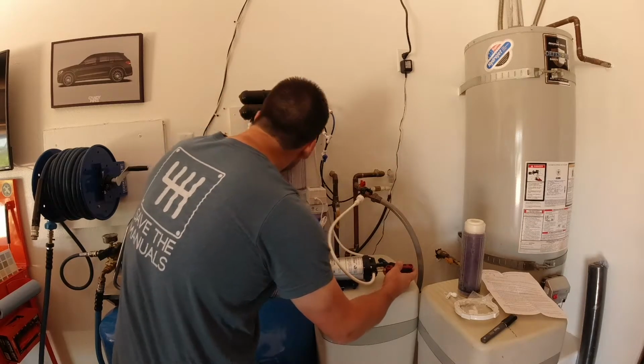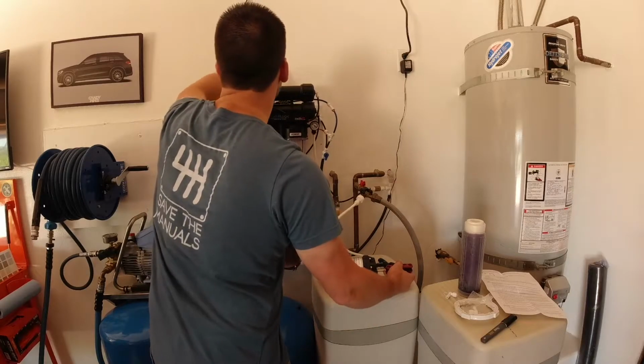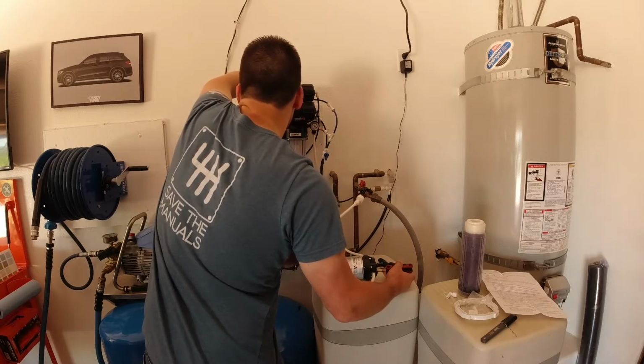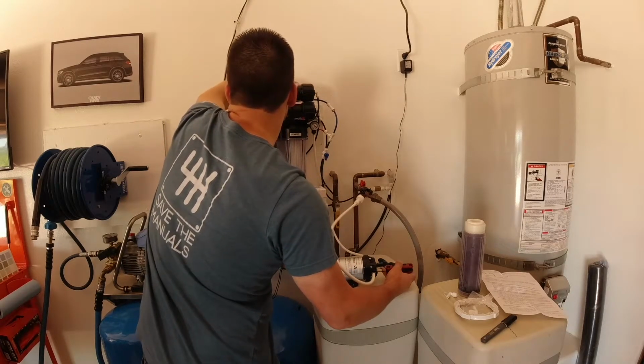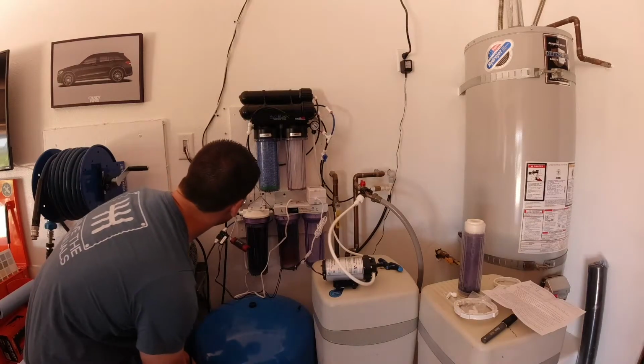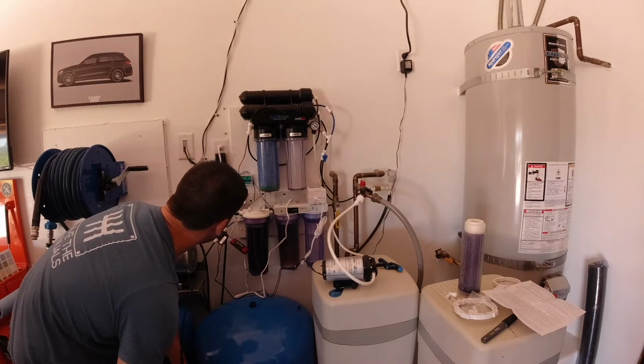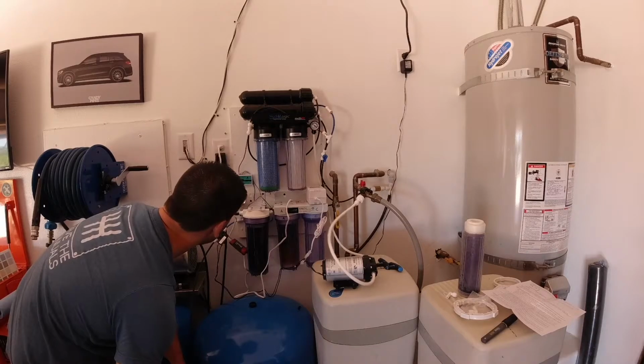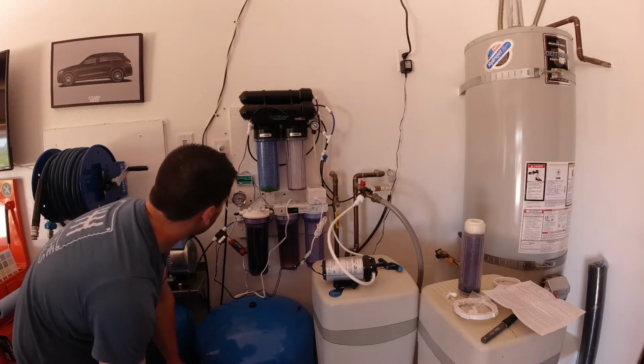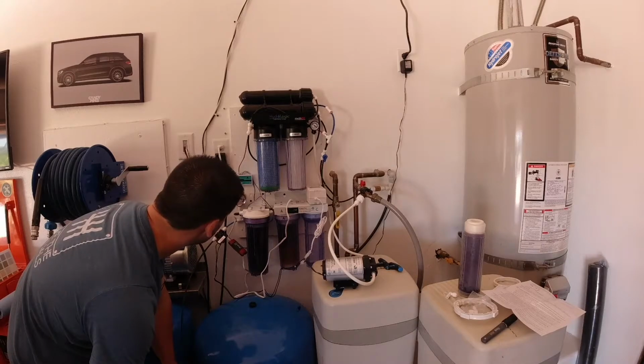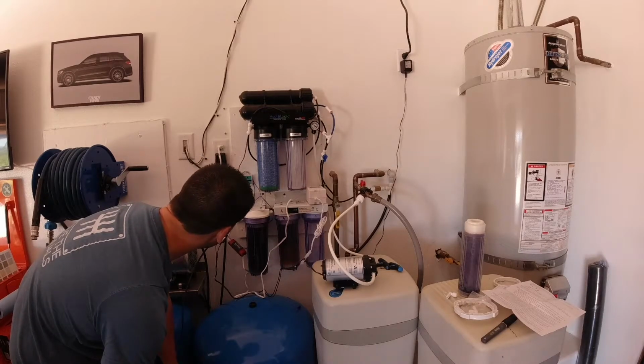When I turn it up too high, I saw some water being forced out of probably this valve on the back. Okay, let's test our off pressure. What I'm doing is blocking the output line. Okay, so it shut off right at 40.